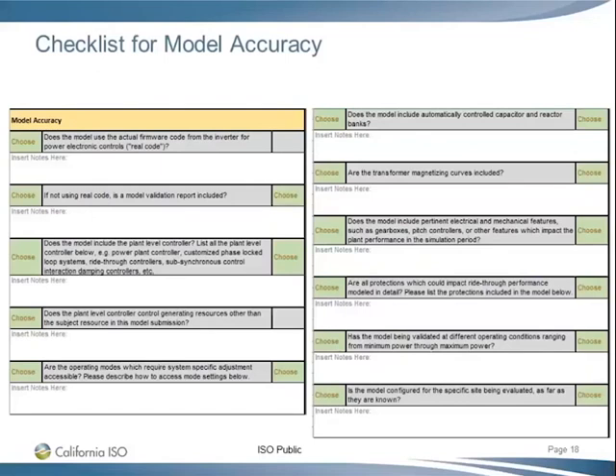Yes, that's the first step you are going to do. Use the generic model and tune the parameters such that it matches the positive sequence model for now. In the long run, we will recommend you collect disturbance data. If an actual system event happens near your plant, use that disturbance data for further refinement. We don't know when that will happen. For model validation purposes, we will accept the model after benchmarking with positive sequence. In the future, we'll keep an eye on any system events that could be used to further validate and tune the model. But at the moment, benchmarking against the RMS model, which has been tuned based on the model test, is acceptable for the time being.